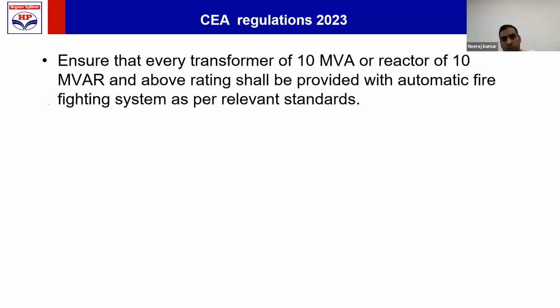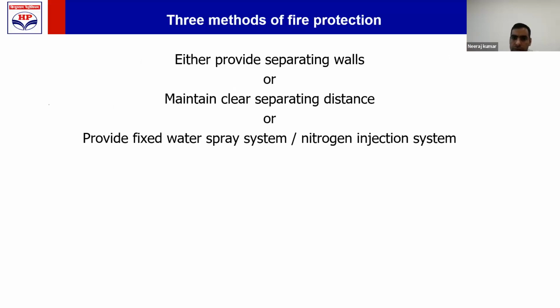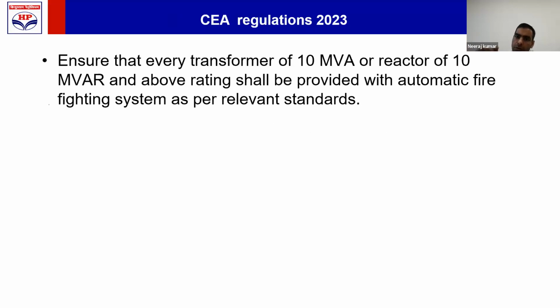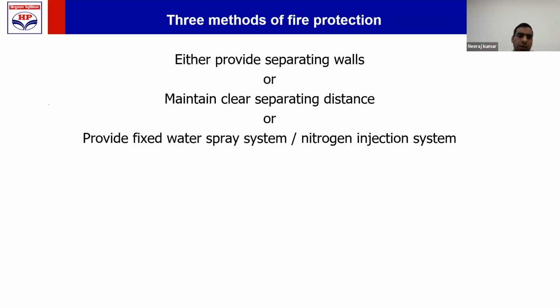If MVA capacity is more than 10, then along with meeting the requirement of OISD-173 that we just discussed, we also have to consider an automatic firefighting system. That will ultimately be your high velocity fire water spray system, or nitrogen system.